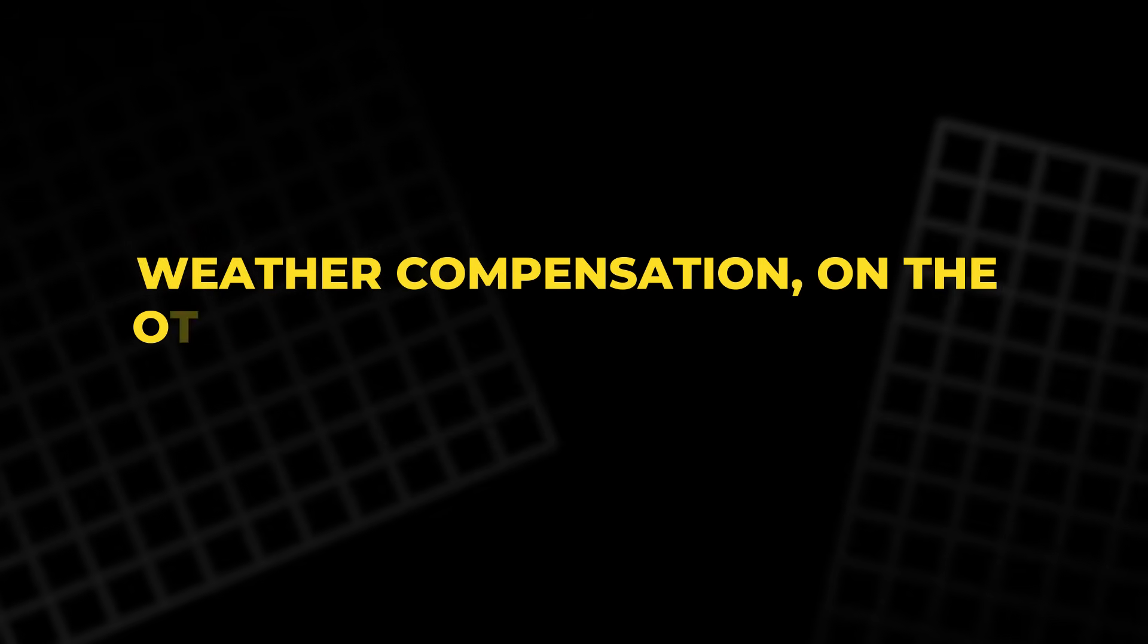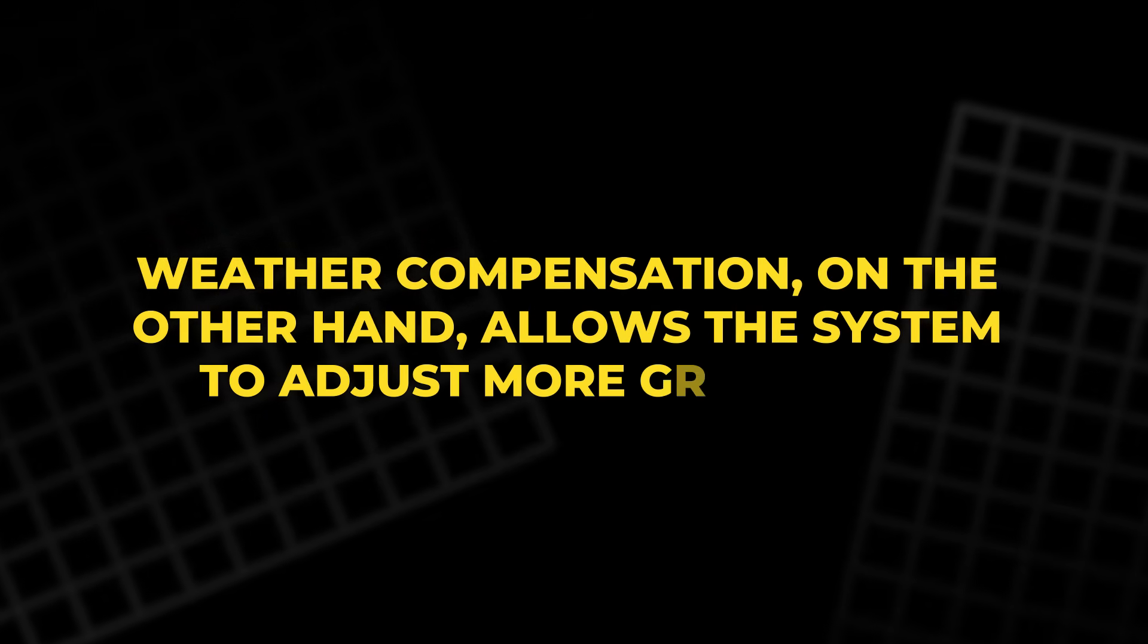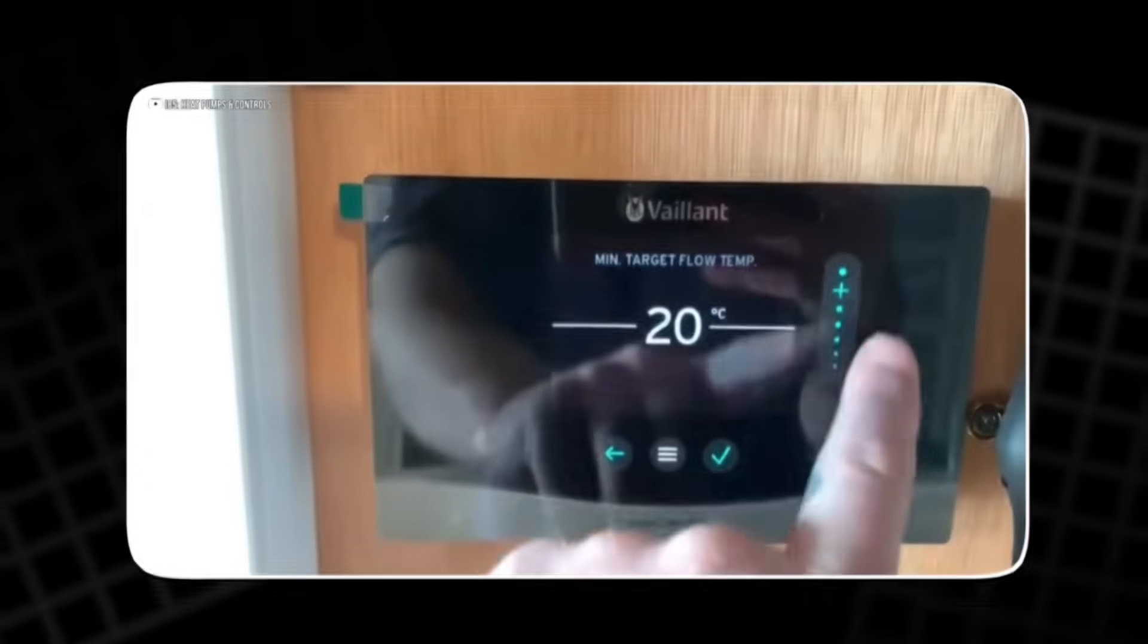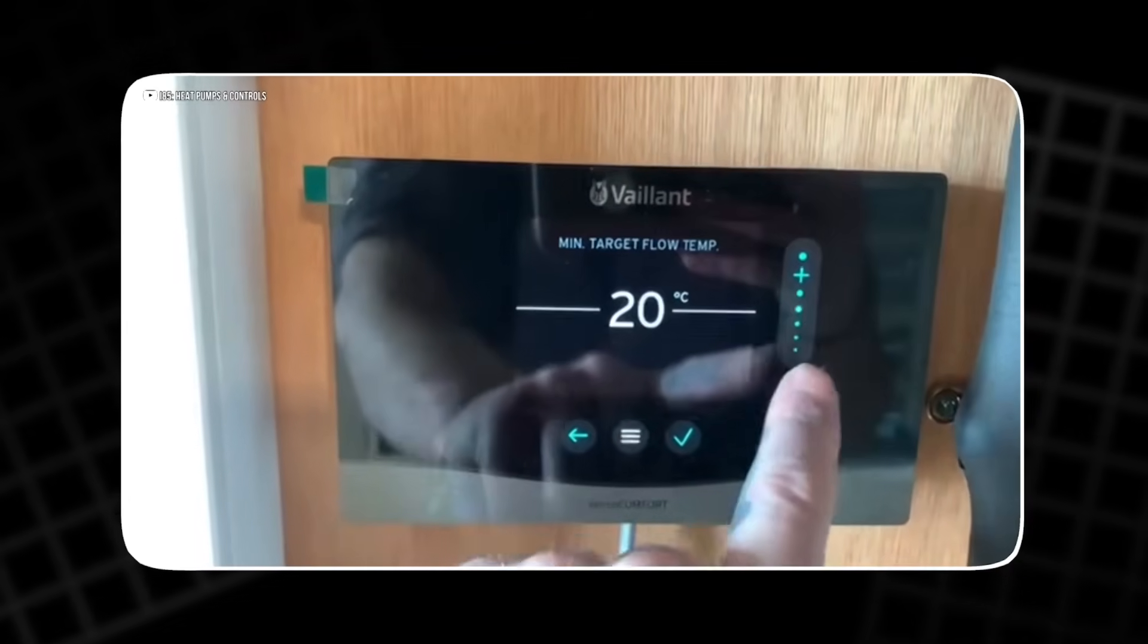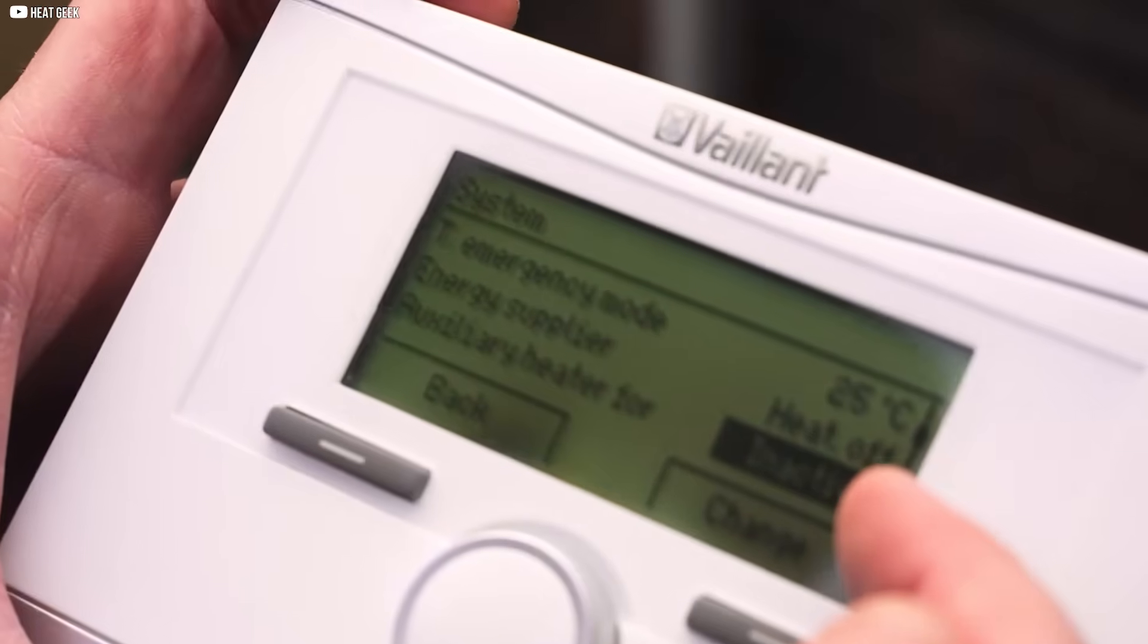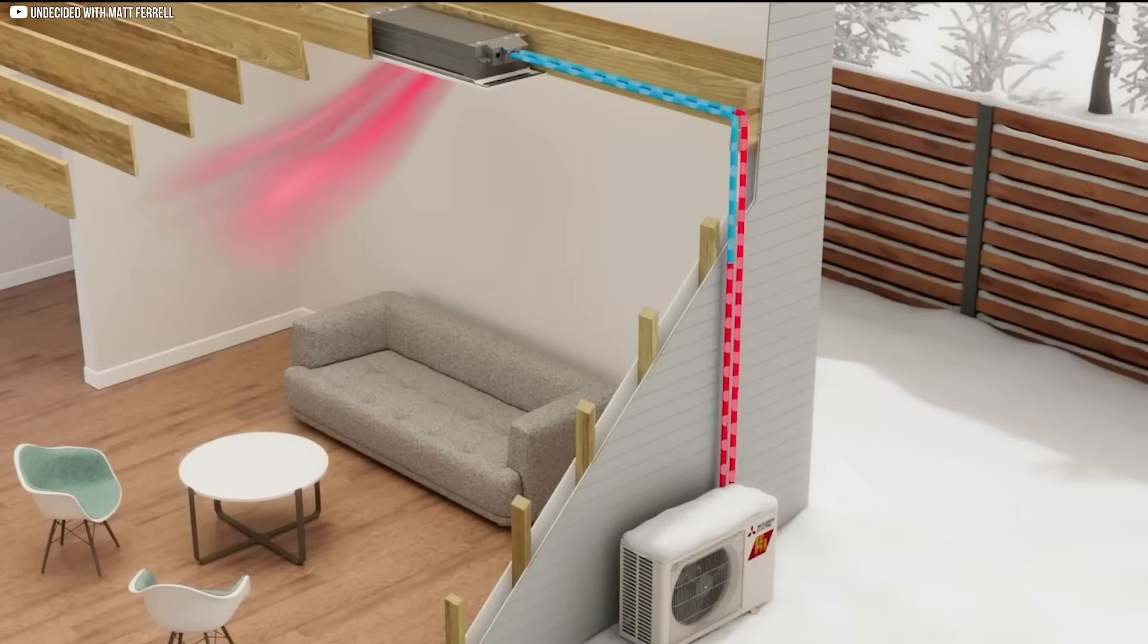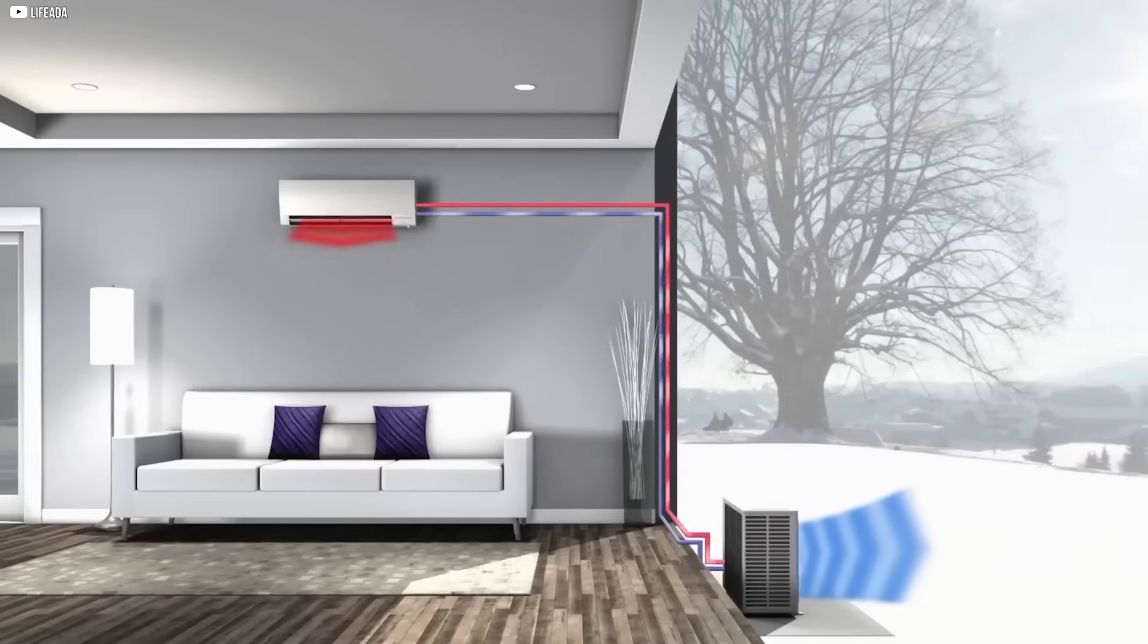Weather compensation, on the other hand, allows the system to adjust more gradually. Instead of turning off completely when the target temperature is reached, a modulating system uses sensors to monitor both indoor and outdoor temperatures, making small adjustments to the heating output. If the outdoor temperature drops quickly, the system will preemptively boost the heat, ensuring a smooth transition without large temperature fluctuations indoors.